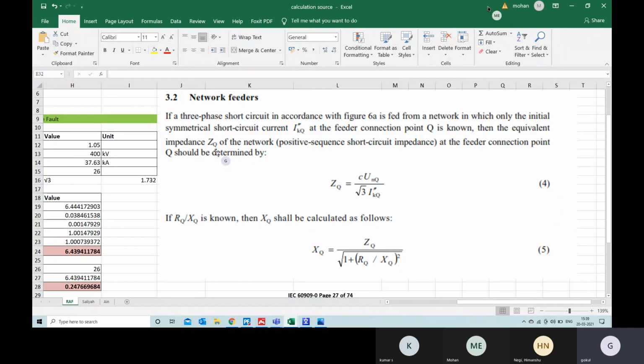Then the equivalent impedance ZQ of the network, the positive sequence short circuit impedance. Here they have not mentioned zero sequence. Do you know when my system will have a zero sequence impedance, or zero sequence current? When there is a phase to earth fault. Exactly correct. When my system has a ground fault, or any line to earth or single line to ground fault, then my system will experience a zero sequence short circuit fault current. But when my system has any fault, there will be a positive sequence current. I know that.